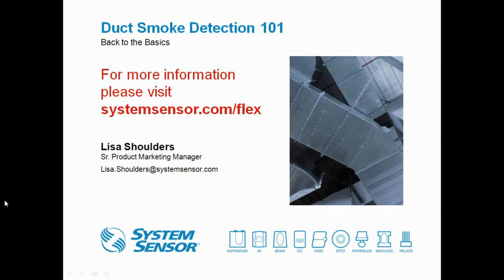The main importance there is to ensure that the exhaust tube that is shipped with the product, so in the parts bag there's a small exhaust tube, is long enough to protrude into the ductwork. If it is not long enough, we do sell a longer version of our exhaust tube that can be purchased separately when it is needed. So if you have an application where that's happening, the part number for that extended exhaust tube is ETX.